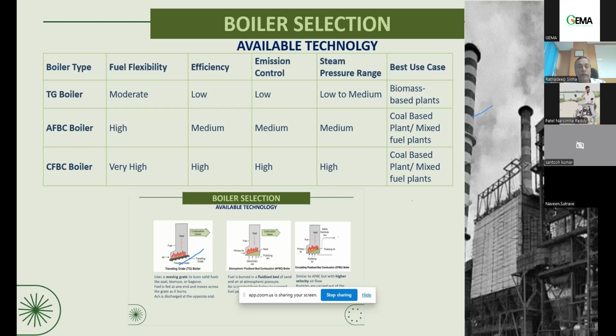Efficiency is medium. It is in between the TG boiler and the CFBC boiler. Emission control, obviously it has some features of emission control, but it is not as high as the CFBC boiler, so you cannot have a very stringent emission control in that. Obviously the particle size is not a problem. With SOx and NOx, it will be difficult to meet today's norm. Steam pressure is medium. I'll come to the next slide where we are going to discuss the steam pressure.